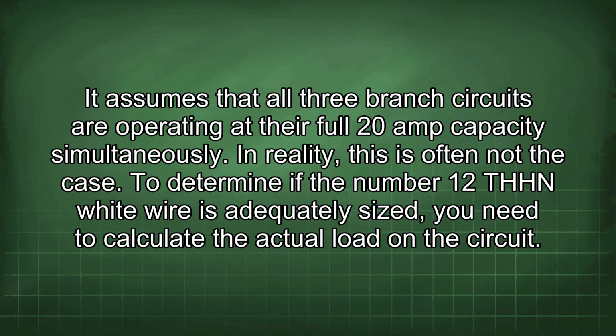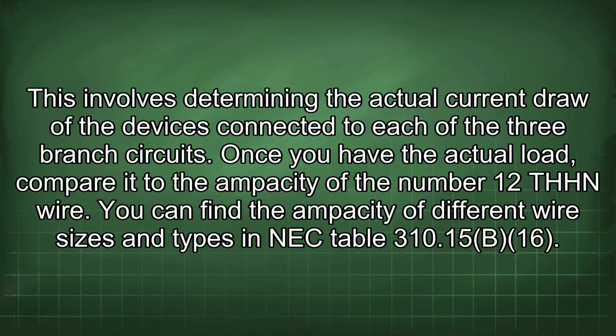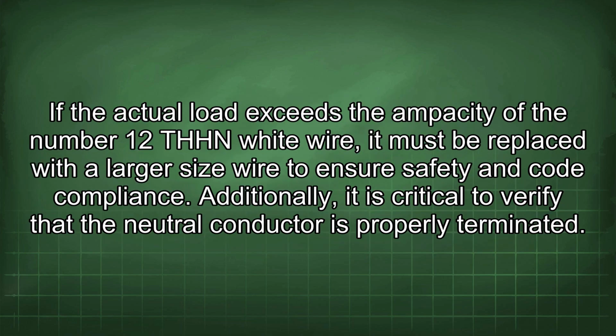To determine if the number 12 THHN white wire is adequately sized, you need to calculate the actual load on the circuit. This involves determining the actual current draw of the devices connected to each of the three branch circuits. Once you have the actual load, compare it to the ampacity of the number 12 THHN wire. You can find the ampacity of different wire sizes and types in NEC Table 310.15(B)(16). If the actual load exceeds the ampacity of the number 12 THHN white wire, it must be replaced with a larger size wire to ensure safety and code compliance.